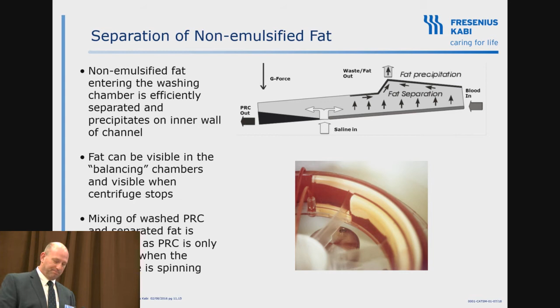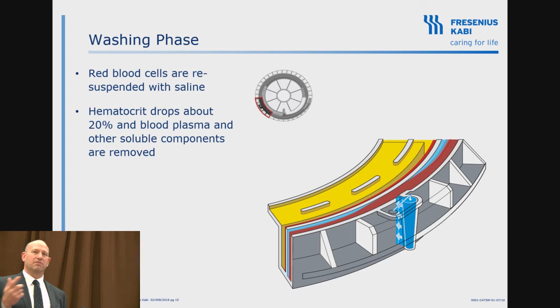So this is the washing phase, which I told you was a little bit different. Notice the channel is the whole width of the chamber, and we actually go straight through the pack and resuspend it. And with the bowl systems, for the most part, they have to wash up against the hard pack and try and create turbulence to get a good mix in there. So you can see the difference in that. The second separation phase, this is at the end of the chamber where the camera is looking at that detection window and the interface. And when it gets a full point that is adjusted by field service people, then we pull out that clean PRC product.